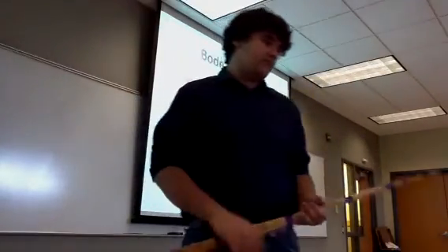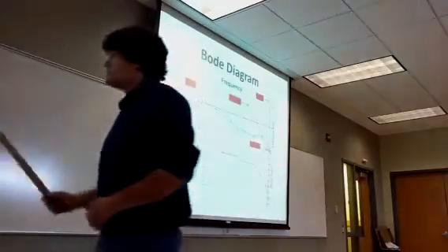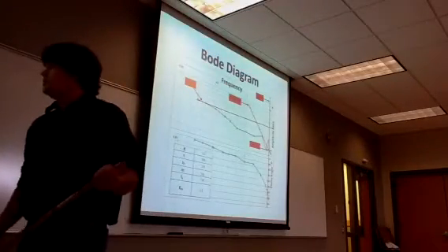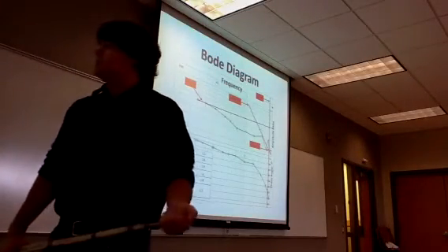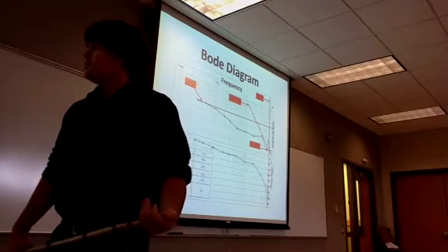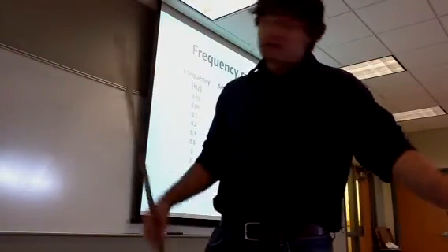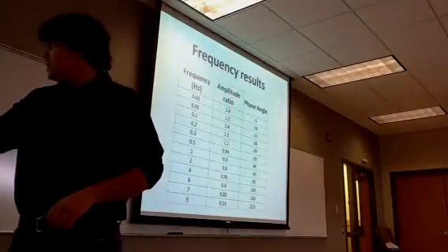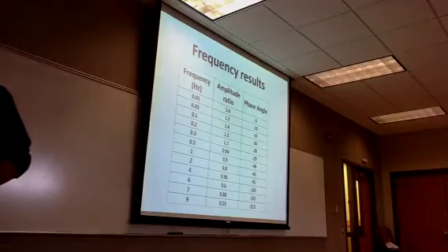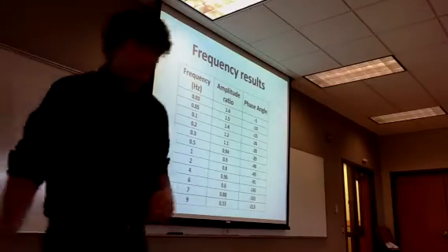And from those results, this is one of 4 Bode plots that we came up with. The K in this is 1.5, the tau is 0.6, the dead time is 1.9, the ultimate frequency is 7.8. You can see if you go back to this chart right here, negative 180 degrees would be the ultimate frequency, and 7.8 is just in between those.